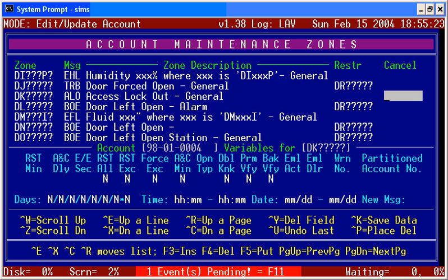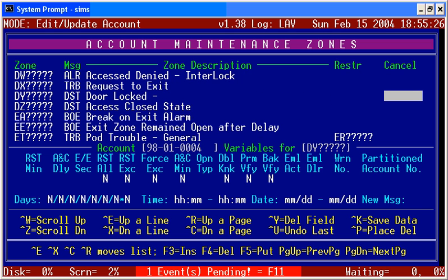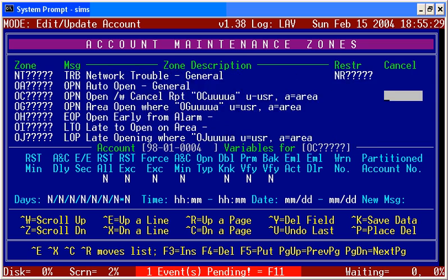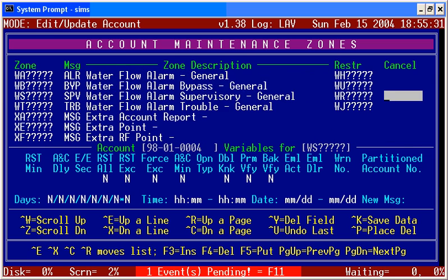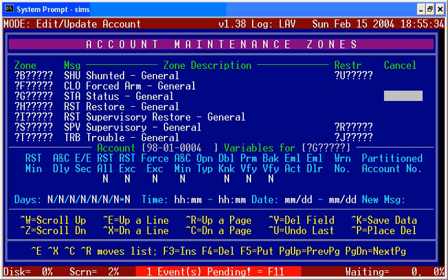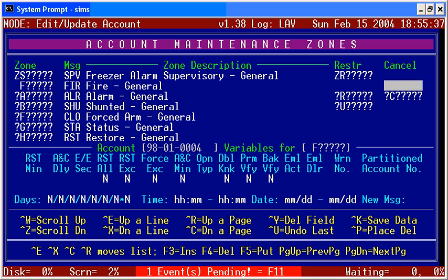If you look through these, you're going to just see lots of different capabilities of the zones. If you go all the way down to the end, we'll find the single character identifiers. If our zone account cannot find the signal that comes in somewhere at the top in the 2 character zones, it will always default down. There are some SIA panels, for example, that might send in a space A for an alarm zone. They don't really identify that it's a burglary or that it's a fire or that it's a tamper or whatever like that. So when you're putting in your zones, again, this is very similar to the contact ID.